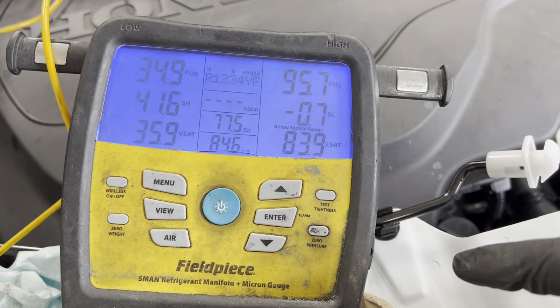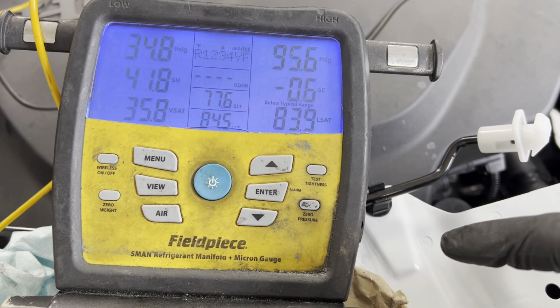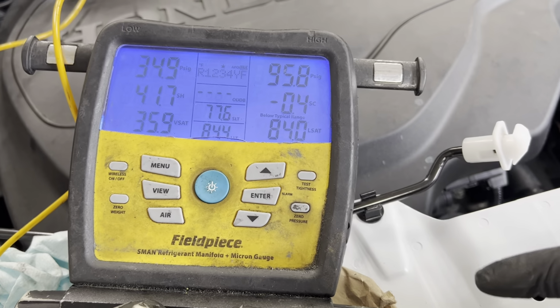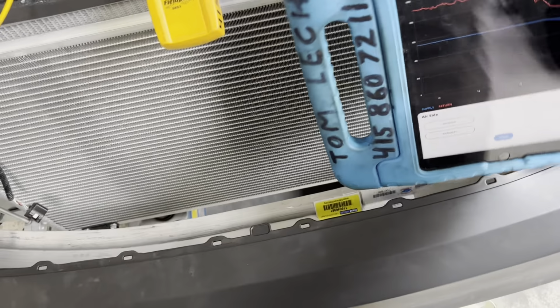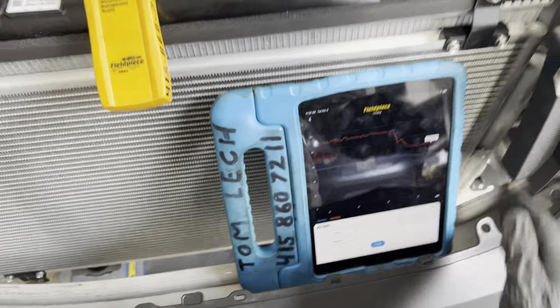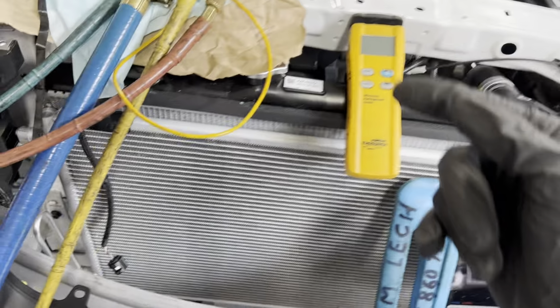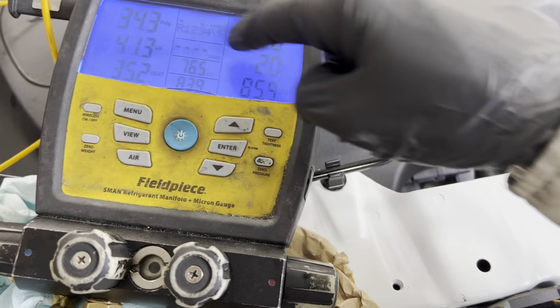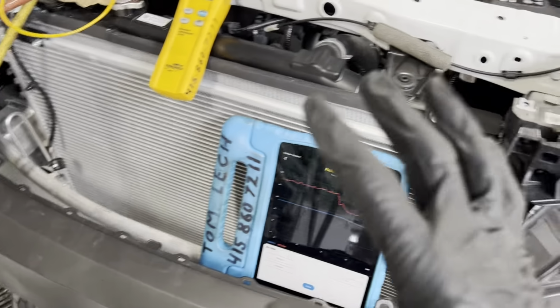Check that out, look at that superheat. It looks like it's starving. Look at that subcooling, it looks like it's starving, but I filled it back up to factory level per the sticker that came on the hood. But if I were to look at that, I would say this vehicle is starving for refrigerant. Why is it starving for refrigerant? I've got to go look back on that hood. I don't like the way that one looks.